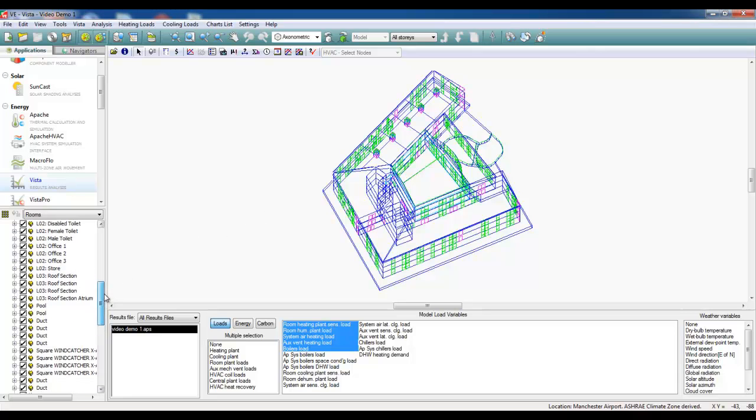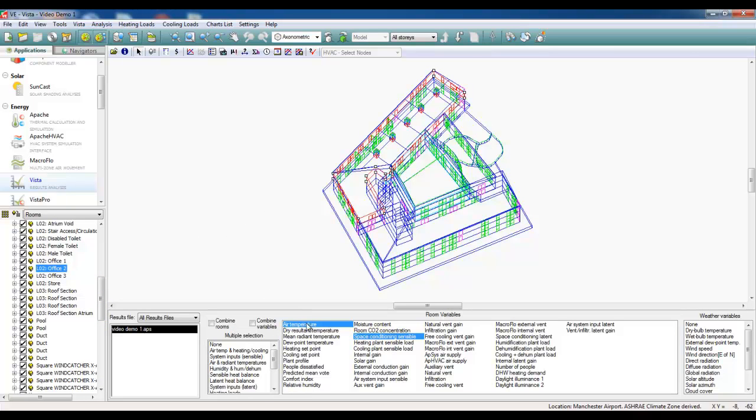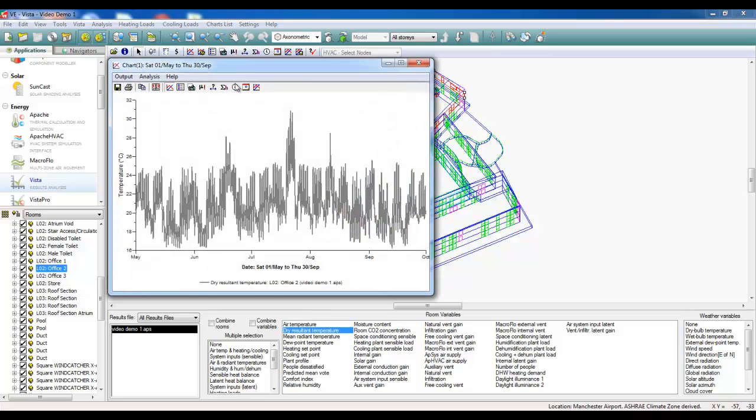Now that we've run our Apache dynamic thermal simulation, we can select the room which our WindCatchers are serving, and here we can analyze our different result sets. We've got the dry resultant temperature here, which we can see is not exceeding 32 degrees over the course of the summer season.